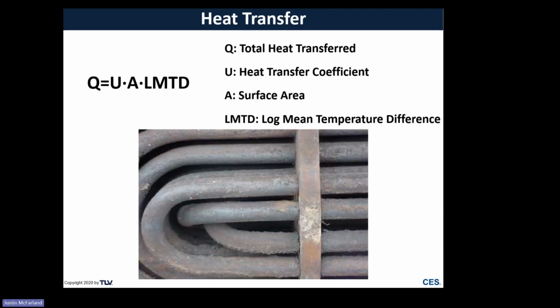So we saw this image earlier, with corrosion and fouling. If something like that occurs, then probably you're going to have a reduction in your heat transfer coefficient. You're going to get rust buildup or product fouling, caking and building up on the process side of the tubes. All that's going to degrade your U value, degrading your heat transfer coefficient, making it more and more difficult for that process heater to provide BTUs to the process.